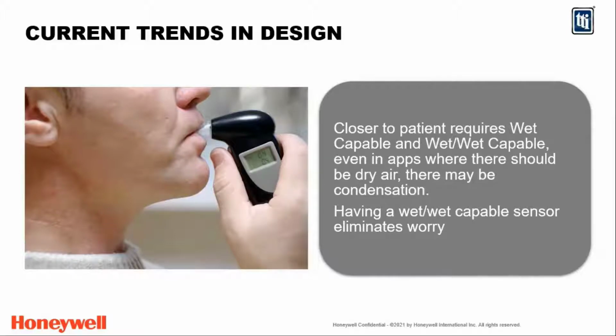That's the good news. The bad news is the closer to the patient that you are means you're going to run into moisture. There's condensation. There's patient breath, and it has humidity in it. And along that length of tubing, you can get condensation. So if you're back at the machine, they've got all kinds of filtering. It's 6 feet away. They actually heat the airflow. It's not an issue. But if you're right at the patient, which is the current trend, you're going to start running into some moisture potential concerns. So you want a sensor that can handle that.